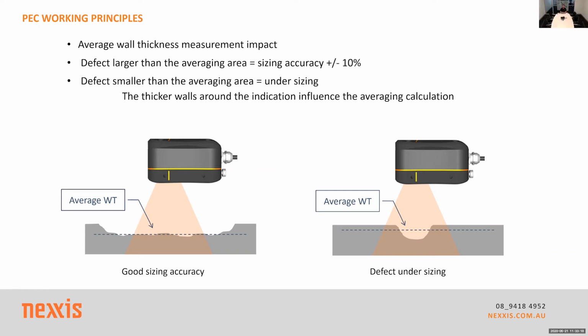Maybe just to expand a little bit on that one, Jarred, maybe the wall thickness range and the insulation coating lift-off range for the 3 or 4 different probes? Yeah, sorry, I didn't cover the probe. In the standard probe range for pulse eddy current, there's 3. There's a small probe, which is your normal stuff. So you're doing a couple inches of lift off and up to about 12, 15 mils of wall thickness. Then you go into a medium probe, which we used for this job.